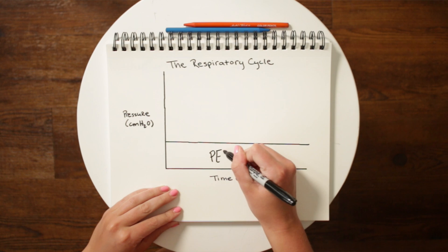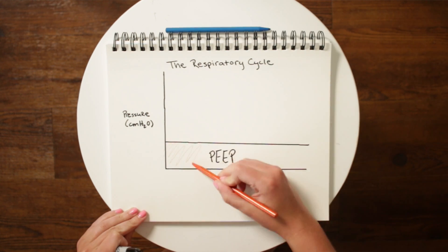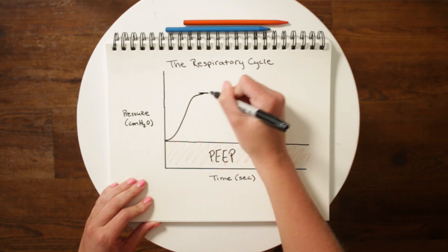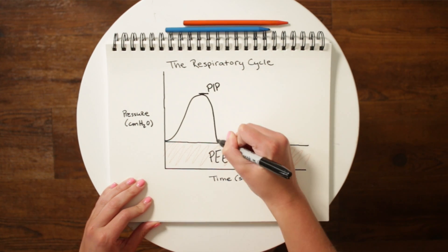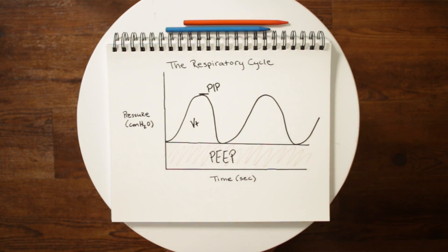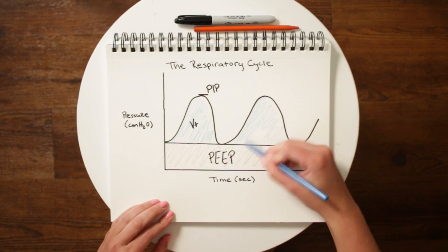On the y-axis we have pressure measured in centimeters of water, and on the x-axis we have time measured in seconds. You can see that PEEP is the baseline amount of pressure left in the lungs after exhalation. When the patient takes a breath, the PIP is the highest level of pressure reached during inhalation. The tidal volume is the amount, or volume, of air delivered to the patient with each breath.